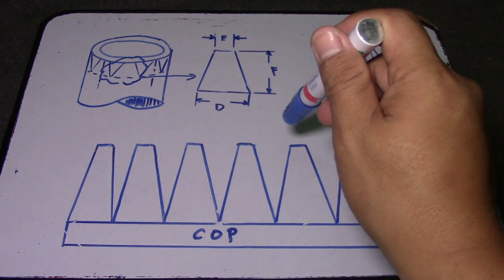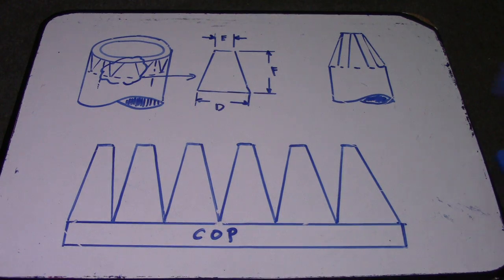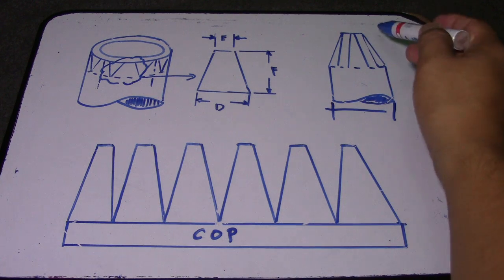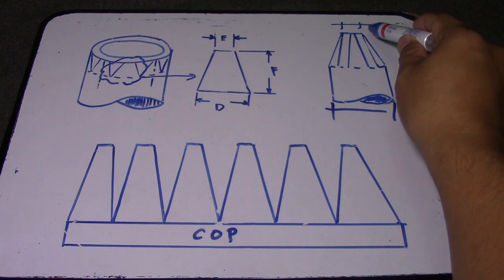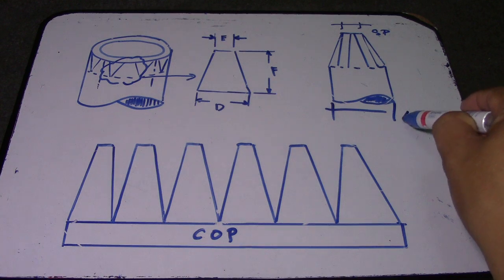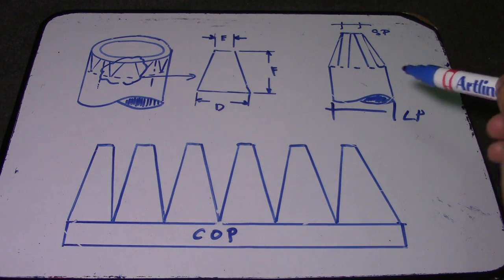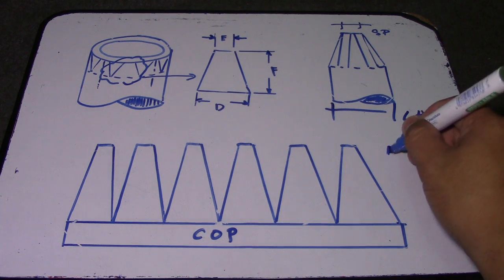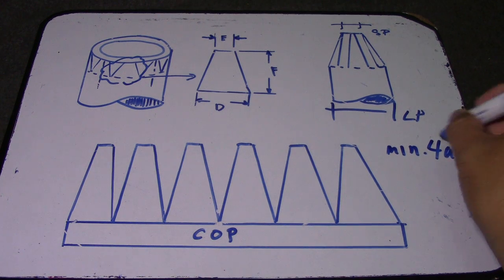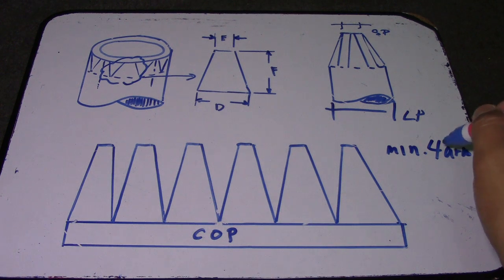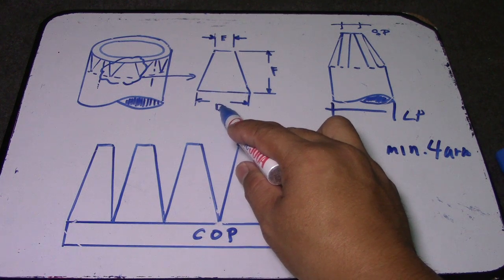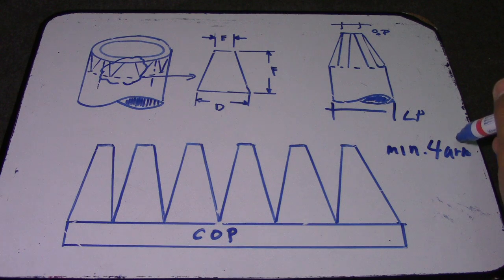To get the circumference of the pipe: 3.1416 times the diameter. That is how to get the circumference of the pipe. Our large pipe is this one and the small pipe is this one. So circumference of the large pipe divided by four — that is our minimum number of arms — gives us letter D.